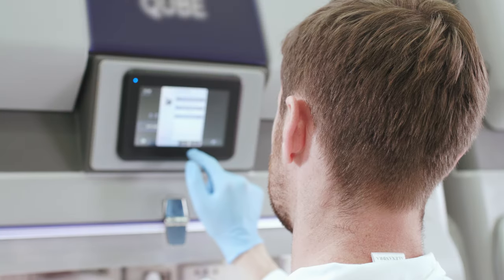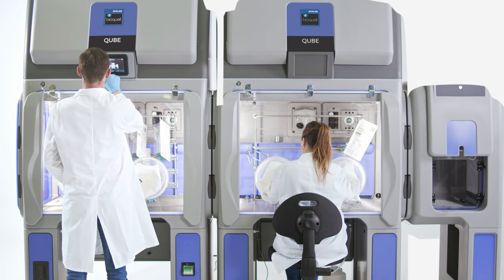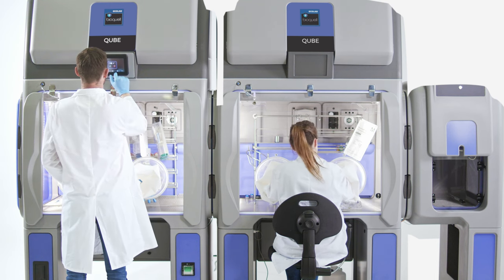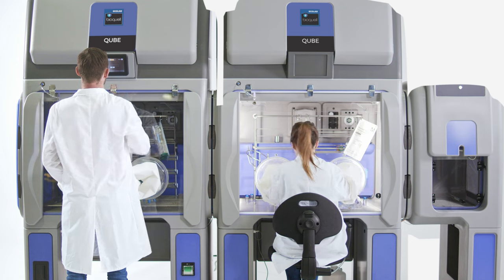Capable of running at either positive or negative pressure, the Bioquell Qube can operate without being ducted into the HVAC as airflow is managed internally. If hazardous materials are being used, there is an option for external venting.